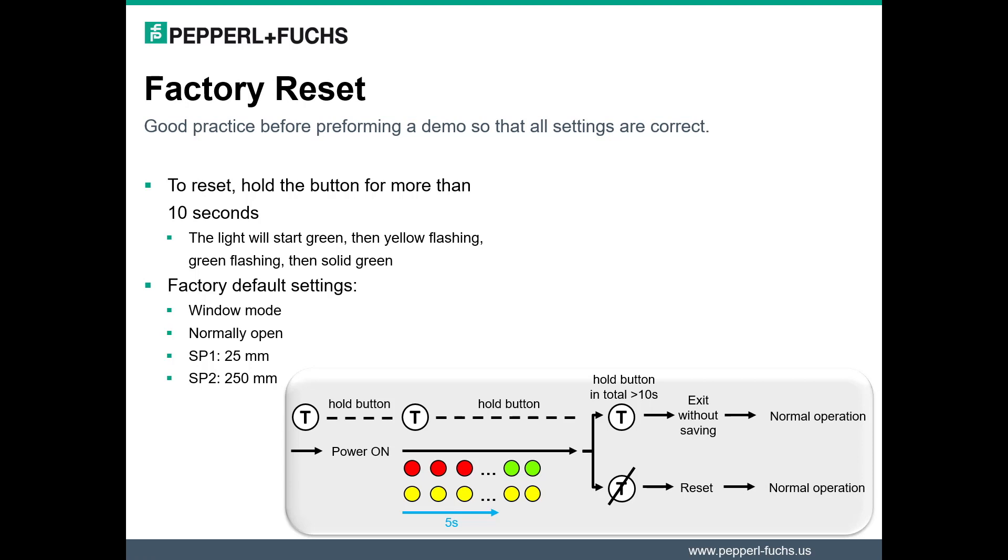Once it is solid green, you can release the button and the sensor will have been reset. The default settings of the sensor are window mode, normally open, and then switching points at 25 and 250 millimeters.